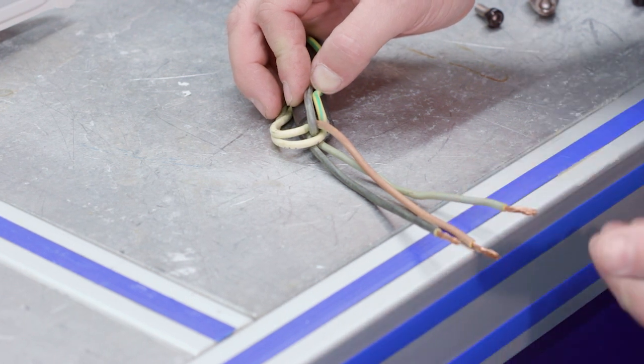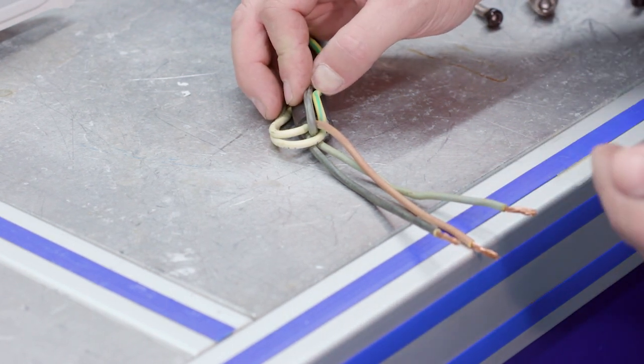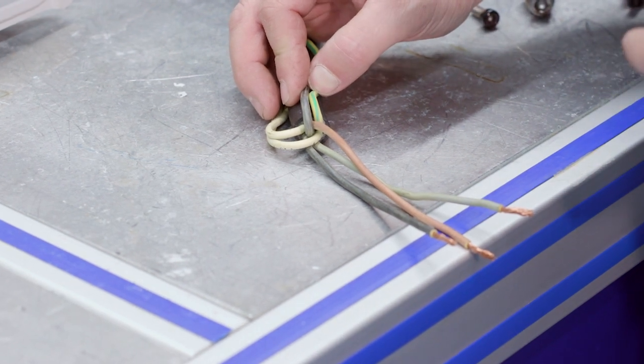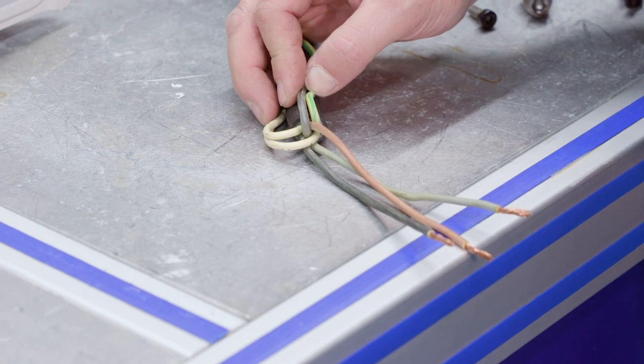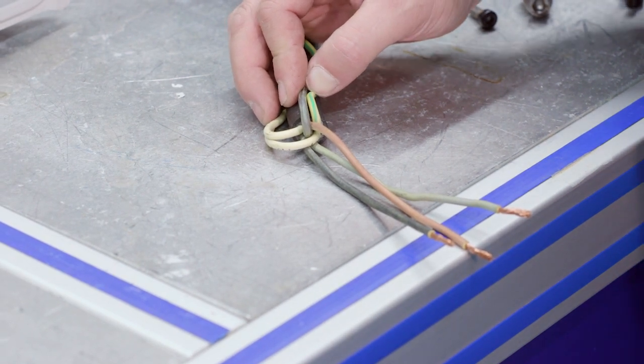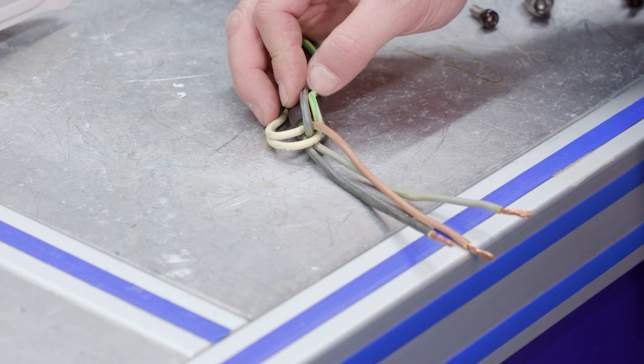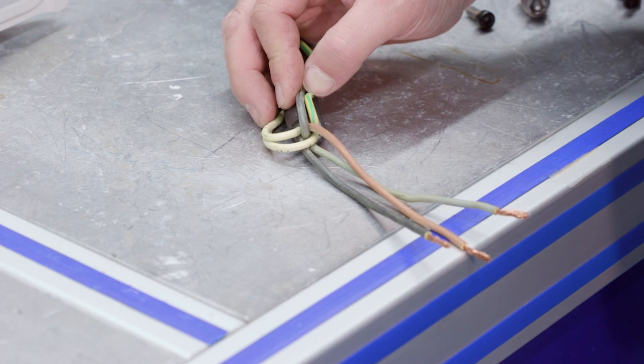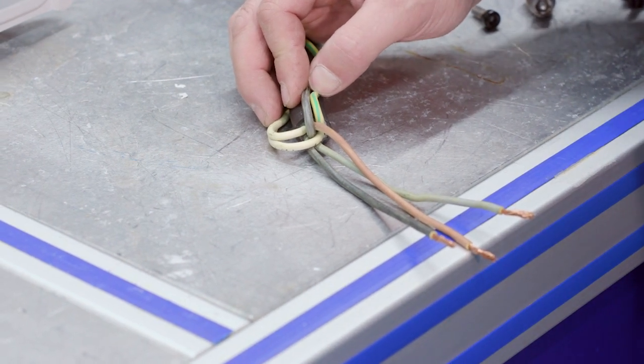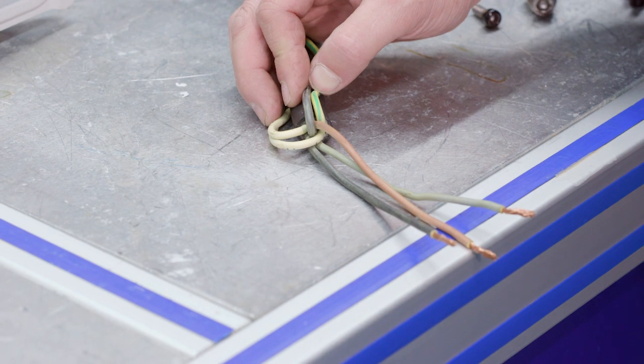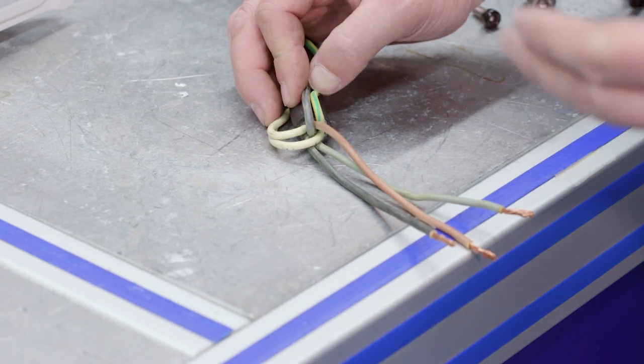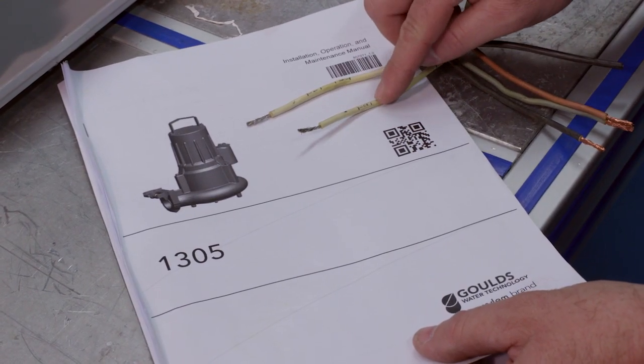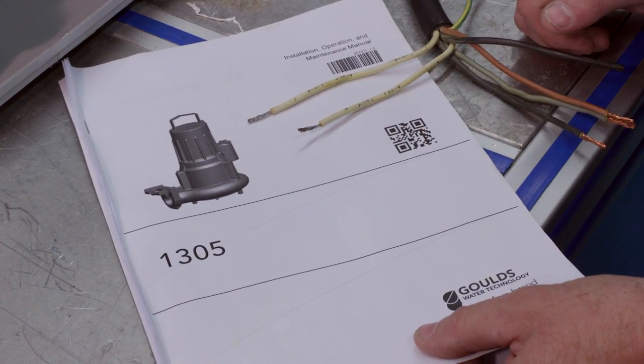This goes to T1, T2, and T3. Just like any three-phase pump, you just wire it up and you need to check the rotation to make sure they have the proper rotation. How do I do that? At the end of the day, it's the best flow and head that is the correct rotation. If we've identified that it is going in the reverse rotation, I just change any two leads on the output or the pump side. Now we have to identify T1, T2. We know these are the sensor wires—one is thermal and the other is leak detection—so we got to refer to the manual.